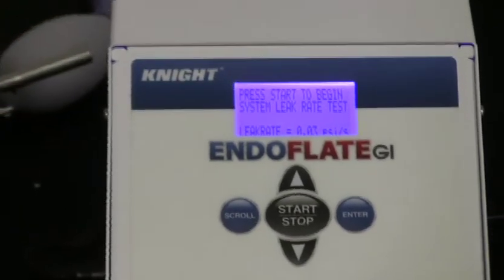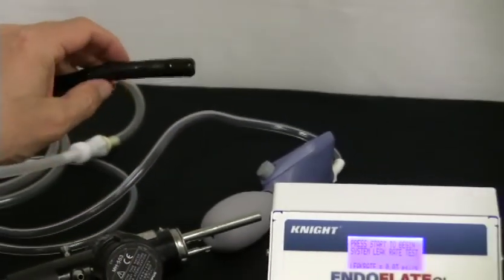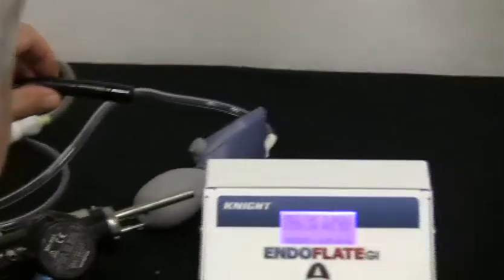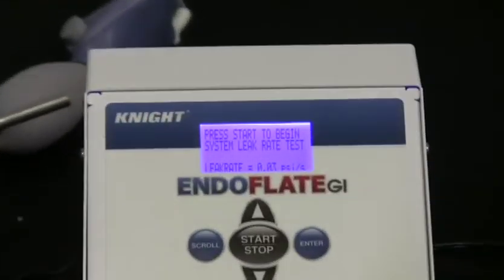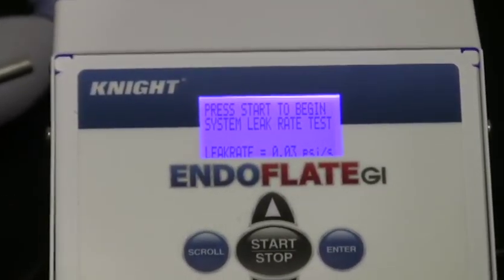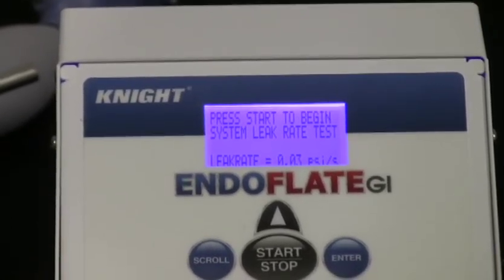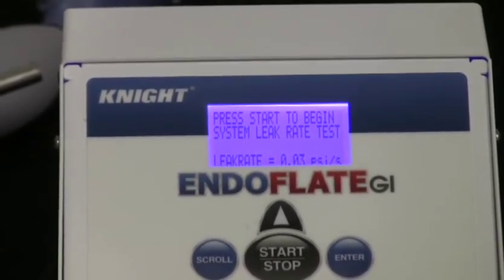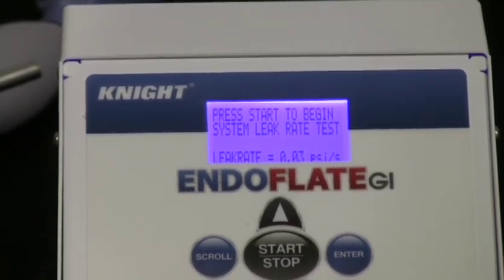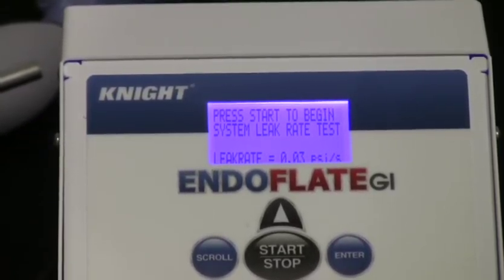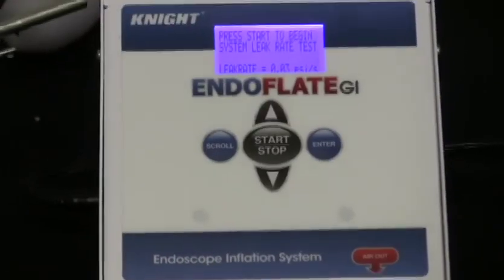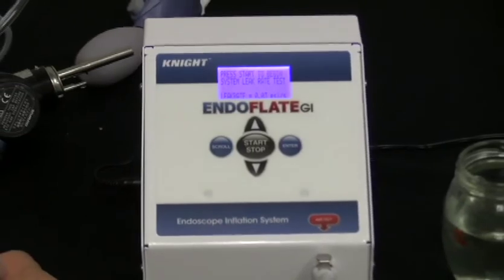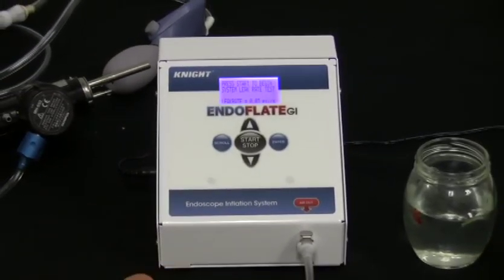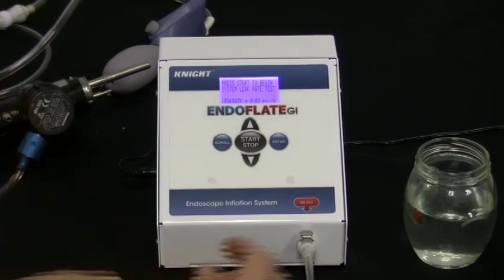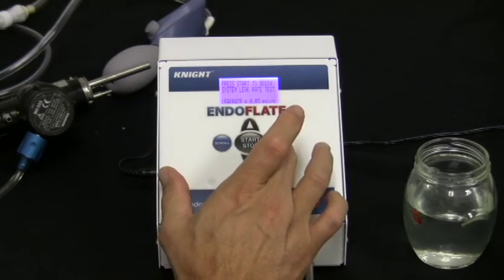We can see that it's inflated. I can feel the difference over here. And the leak rate it's showing me is 0.03 psi per second now. That's holding really well. Okay, so the leak rate is very, very small, if any, and that may be the tubing connections here and not have anything to do with the scope, but clearly the scope sheath and the liner is not compromised in any way, and we're in good shape to finish processing the scope. Hit enter here, get out.